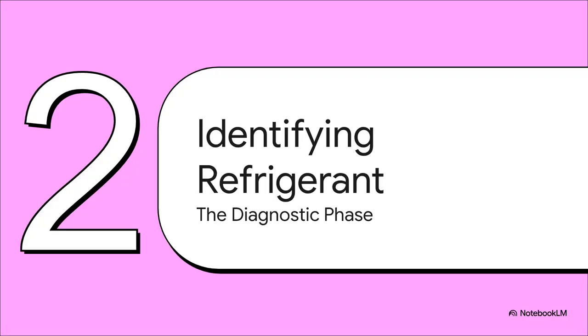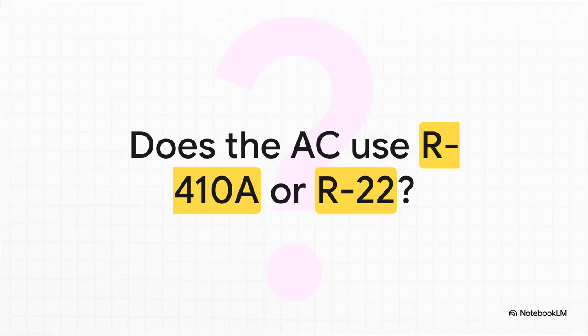Moving on to Section 2, Identifying the refrigerant type. This is your diagnostic phase. Picture this. You walk up to a unit. The manufacturer's data plate on the side panel is faded, or maybe it's just completely gone. How do you know if you're dealing with older R22 or the newer R410A without risking a dangerous blowout? You have to know for sure because virgin R22 has been banned for servicing in places like the EU for years now. That means it legally cannot be recharged.